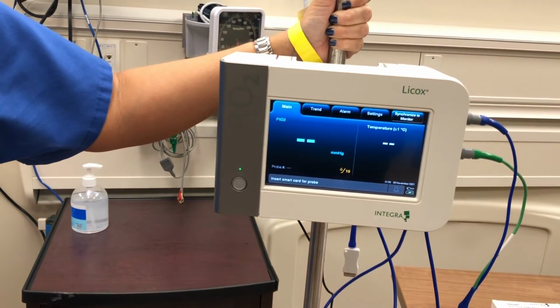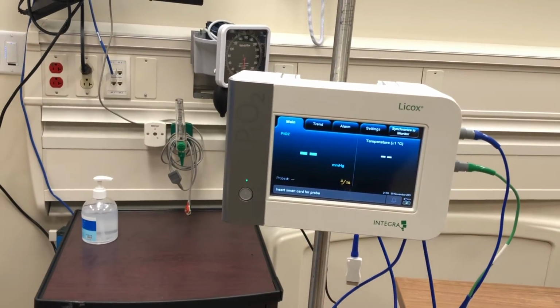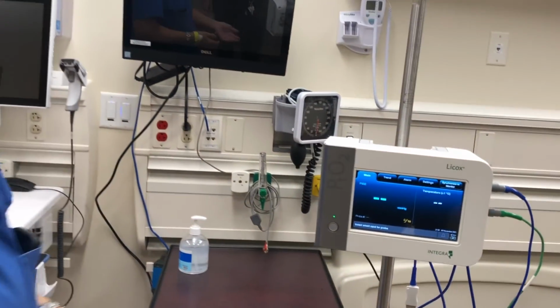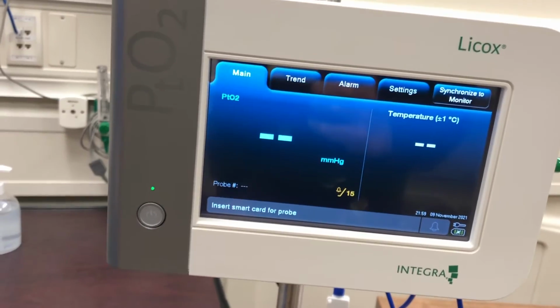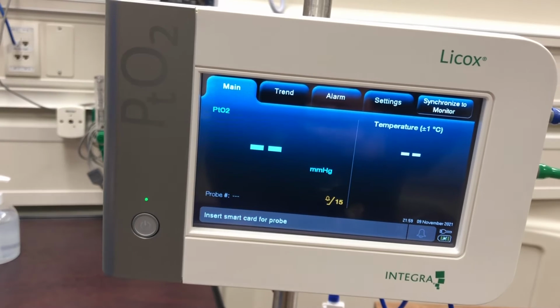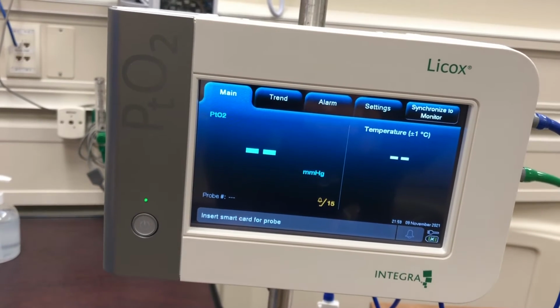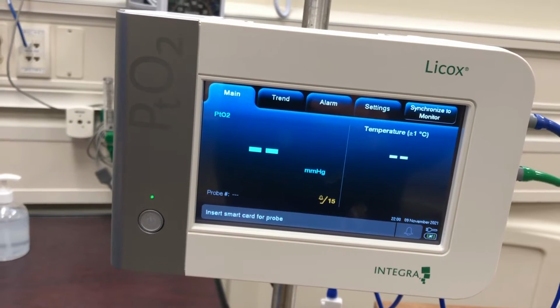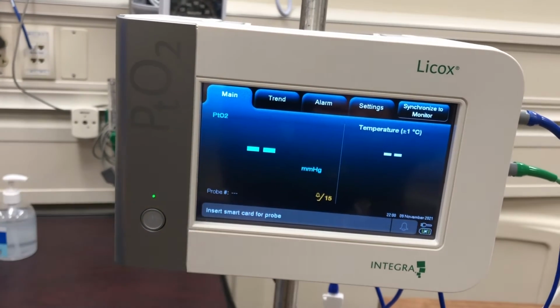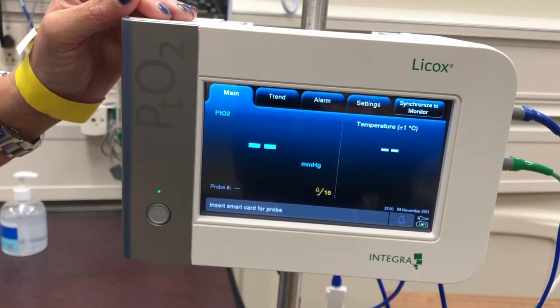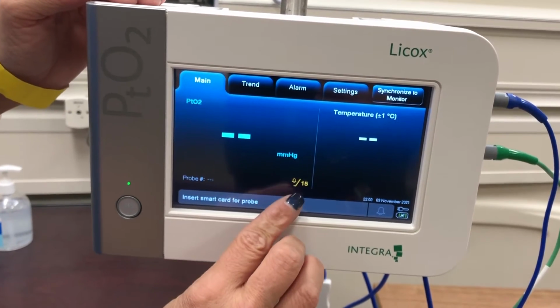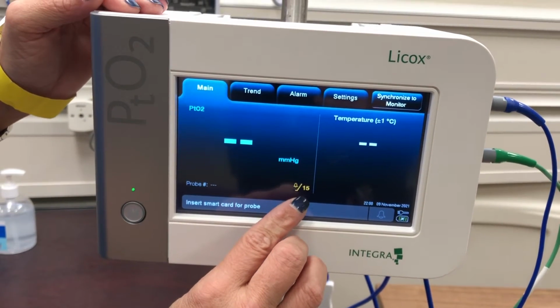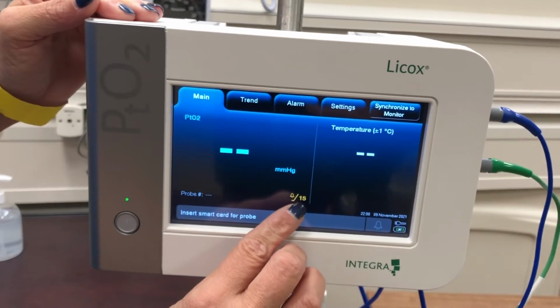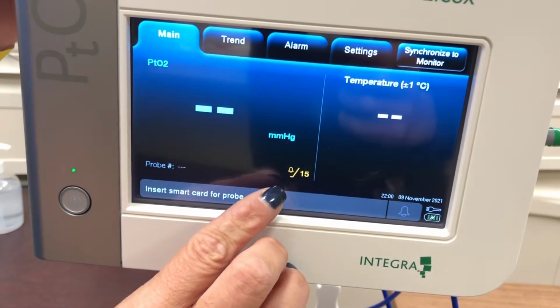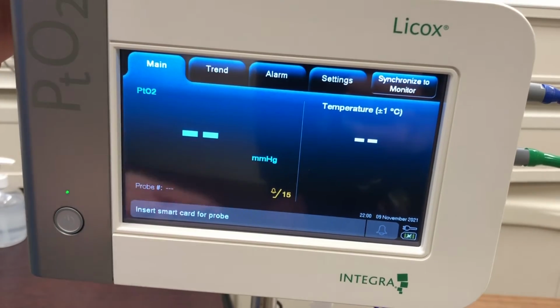But in the midst of all of this, you're going to be getting set up for your actual insertion. Just to orient you to the screen a little bit, on the left-hand side of the screen you have PTO2, same thing as PbTO2. We say PTO2 because this monitor is also used in Europe for tissues other than the brain, so it is a partial pressure of oxygen within the tissue. So you have 2 dashes there, which lets me know that there's nothing connected to it right now. You'll see this little marking that looks like an alarm bell, just like you would expect. And underneath that is the threshold, the default. There is a default setting on the alarm of 15. I see that just by looking at the main screen.